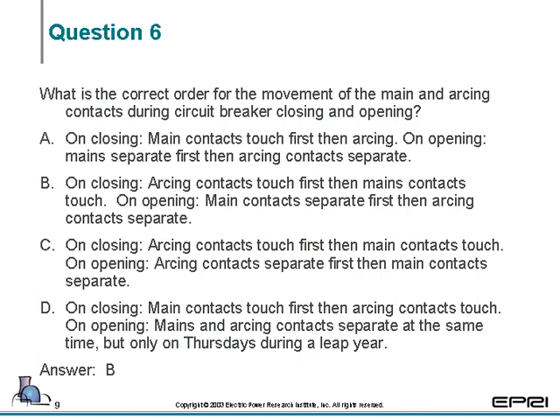Question 6. This is the one we read wrong, but corrected our mistake there. Question 6, what is the correct order for the movement of the main and arcing contacts during circuit breaker closing and opening? The answer is B. On closing, arcing contacts touch first, then the main contacts touch. On opening, main contacts separate first, then arcing contacts separate. The arcing contacts are kind of destructive in nature, but they are there to take the arc and the pitting. And Gene mentioned that on arcing contacts you'll likely have pitting, and the object of the arcing contact is to protect the main contact, because after the breaker is in the closed state, the main contact will carry the majority of the load. Yeah.